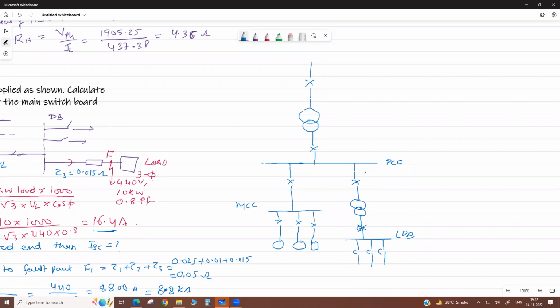Why do we use a lighting transformer? For isolation. Supply isolation. First is isolation. Why? It isolates your lighting loads from the main loads, your important loads, motor loads, process loads, okay? Correct? These are the main utility loads.